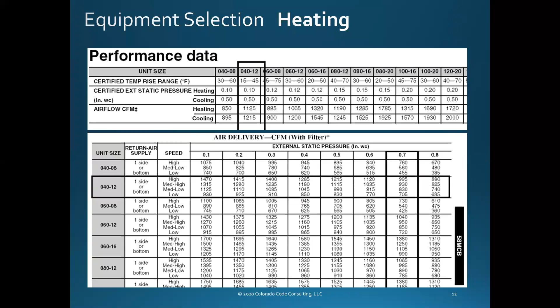One thing here is that if this is all the chart says, and this is as far as it goes, up to 0.8, that doesn't mean I can look at anything that says I've designed to a 0.9. Nope, can't do it. I can interpolate, which means that I can do the math between 0.6 and 0.7 and maybe get 0.65. What I cannot do is extrapolate, which means use the fan math to take this to 0.9 or to 1 inch of static. I cannot do that. This is the chart. That's the one you get to work with, okay? That is a gas-fired furnace, very quickly.